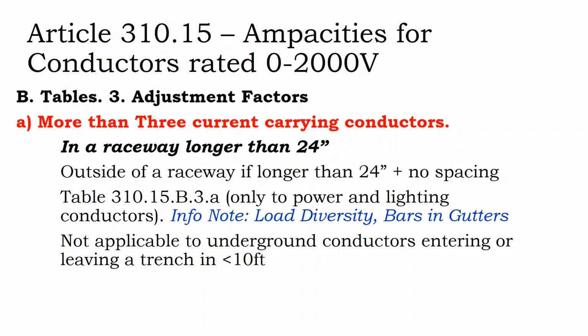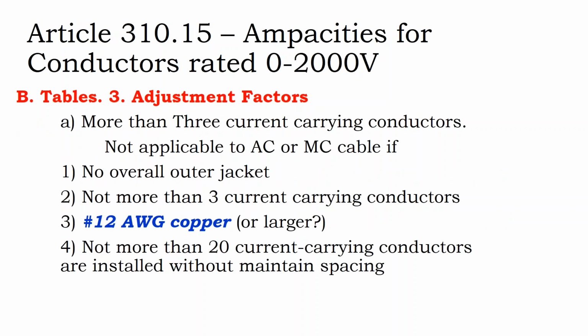Now, if I have one wire in a conduit, it's emitting heat. If I have two wires in a conduit, it's going to have less space inside that conduit. If I have three wires inside that conduit, there's going to be even less space, and different wires with different loads on them producing heat at different times. Maybe some of the loads are continuous, maybe other loads aren't. But the net effect of putting multiple wires into the same conduit is that inside of that conduit is going to be hotter. And so we have to apply additional discount factors if we're putting more than one wire in the same conduit. And so there are adjustment factors that are applicable if you have more than 3 current carrying conductors in a conduit, which would indicate multiple circuits rather than just one circuit.